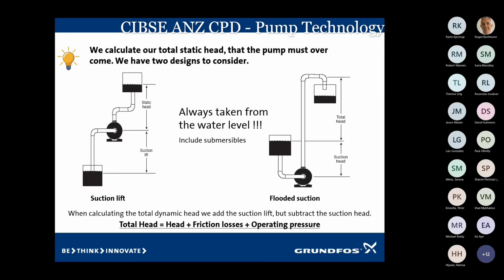So at 20 liters a second, that water is drawn down to 100 meters, but we've got our pump sitting at 200 meters. We only need to start our suction lift from where the well is drawn down to at the 100 mark, not 200 meters. If we start at the 200 meters, we've just oversized our pump hugely, and that's a lot of energy, plus also over-pressurizing. We don't need to over-pressurize the system. So always take it from where the water level is to the delivery point.